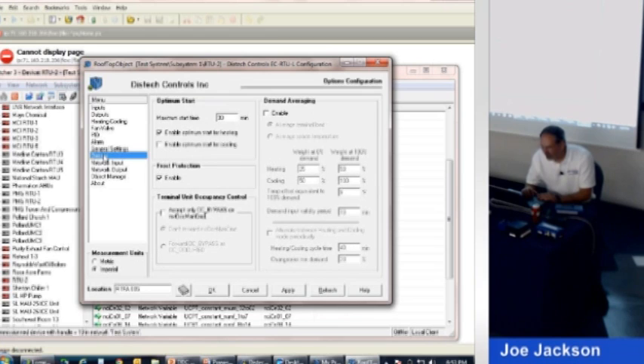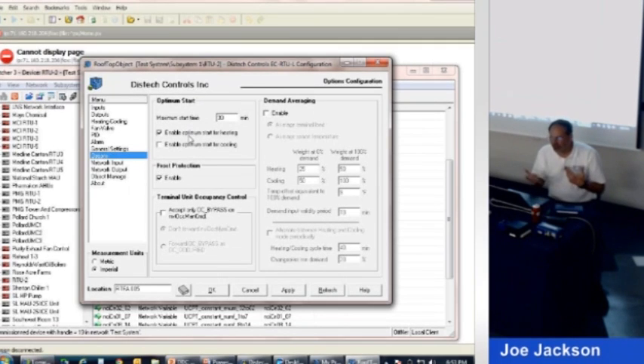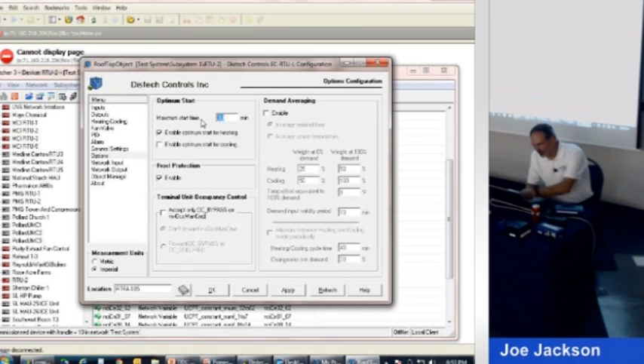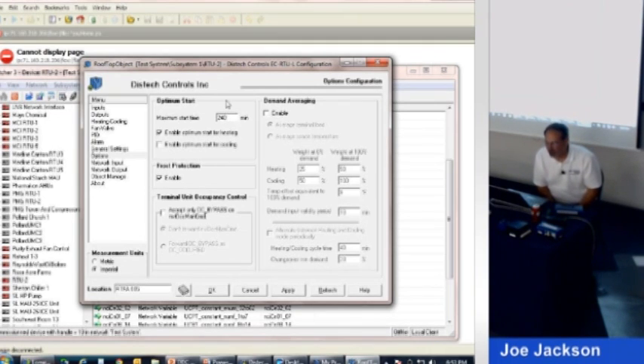Options. It has optimal start-stop. So it looks at what time it's going to go occupied, and if it were me, I'd set that at 240 minutes. That means if it needed to, it could start up at 240 minutes before the scheduled time to make sure we hit set point right on time. And I'd tell it to do that in both heating and cooling modes.